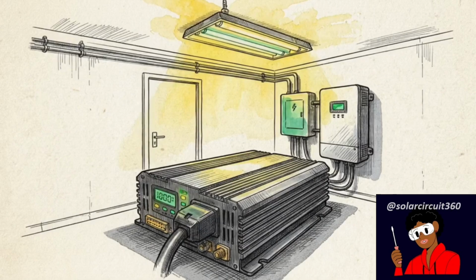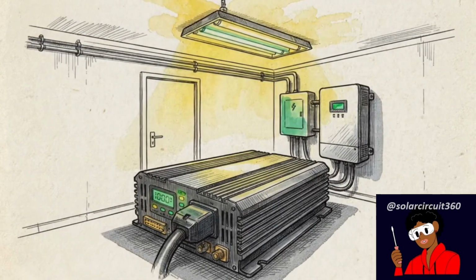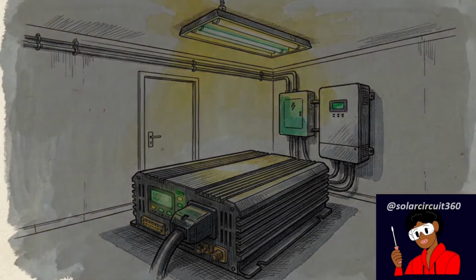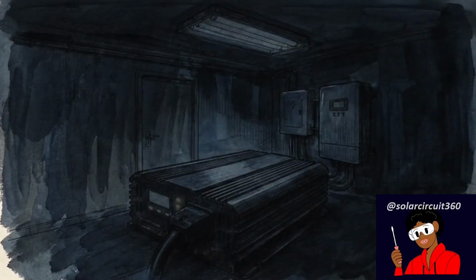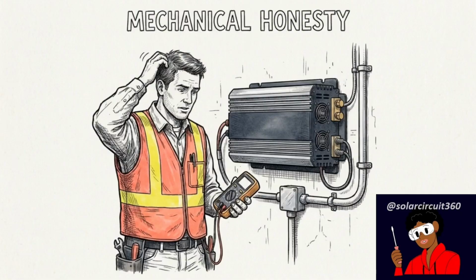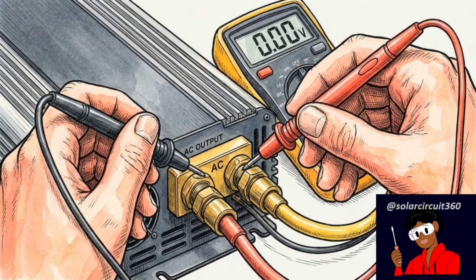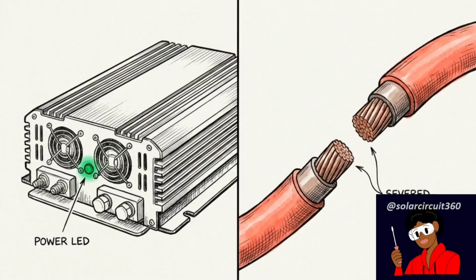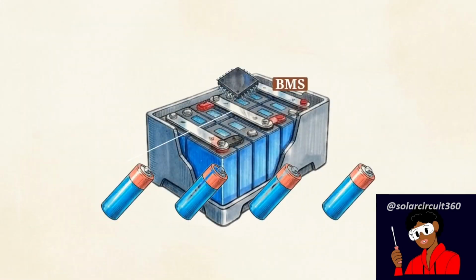A heavy household power load suddenly kicks on, and the entire off-grid backup system instantly goes dark, leaving the utility room in complete blackness. When this happens, field technicians often assume the hardware failed. They check the inverter, see no AC output, and write it off as a blown unit. But the inverter usually works perfectly. It shut down because its direct current power source was suddenly severed without warning. The actual disconnect happens inside the battery.